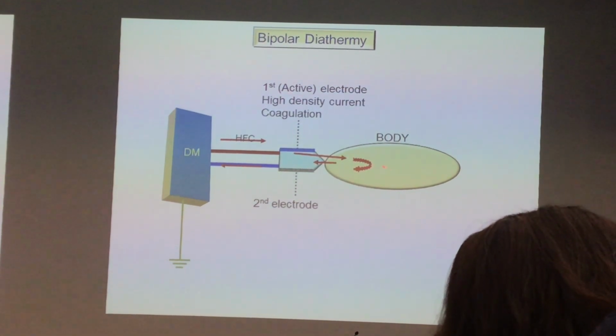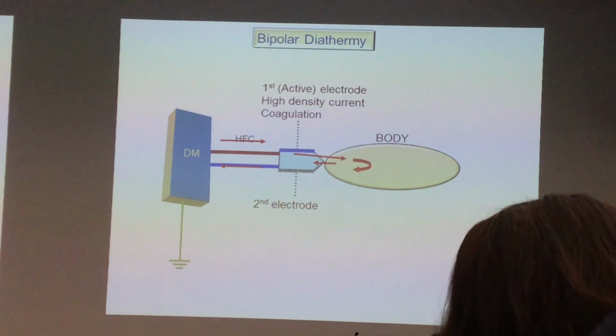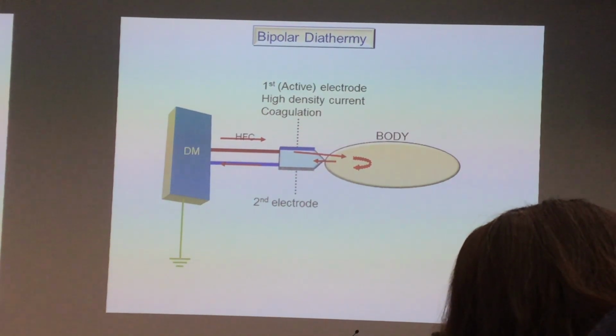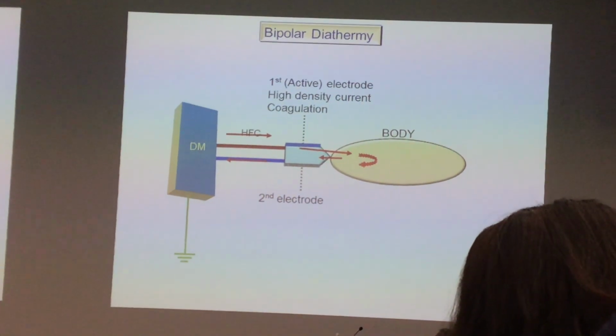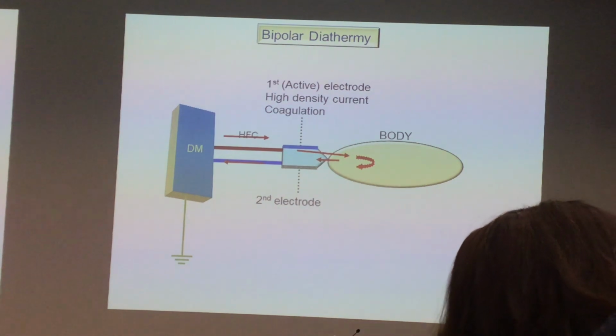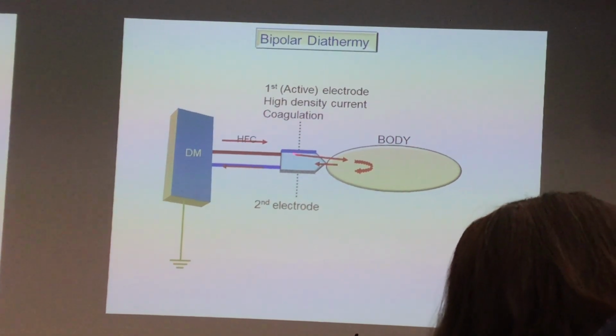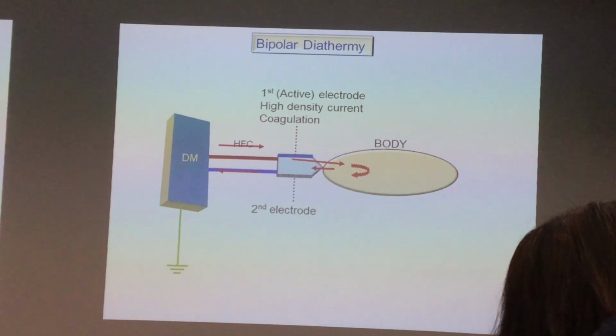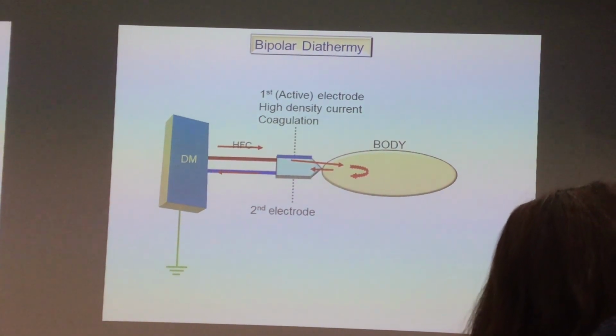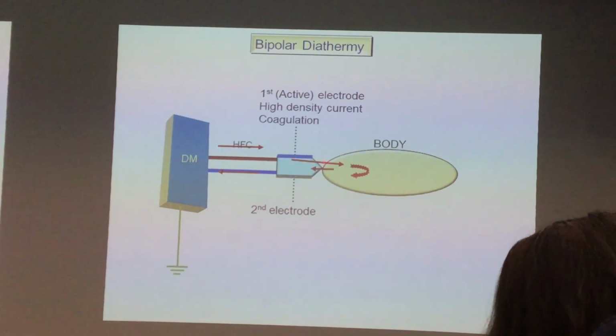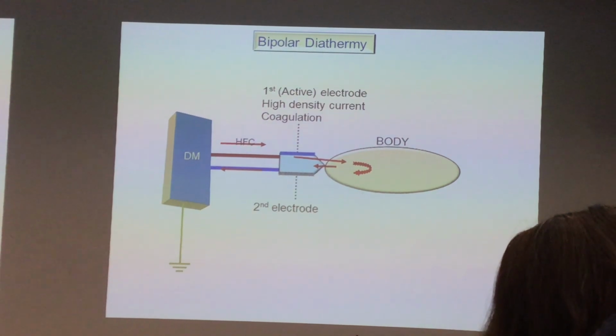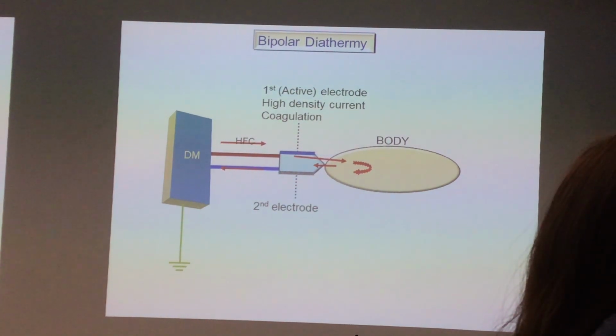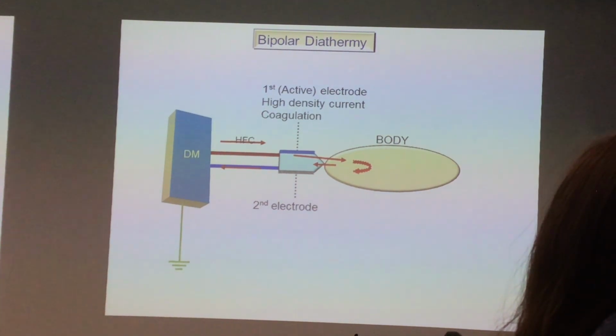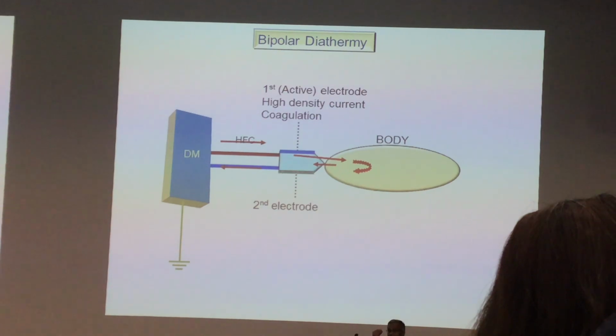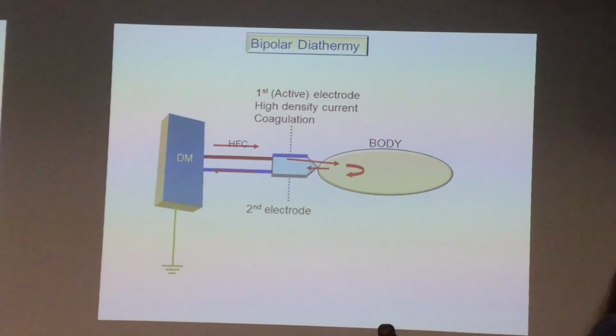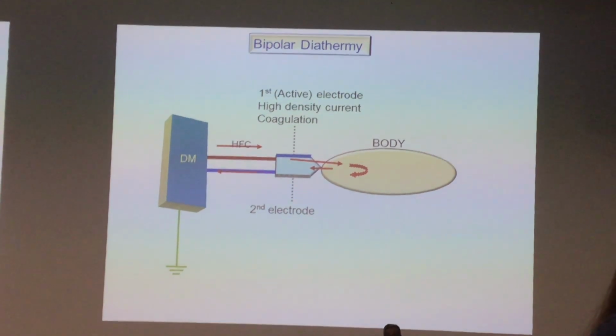In terms of frequency, I think this one needs higher frequency. So I just refresh: for cutting, you need lower frequency, 1 or 2 million hertz. For coagulation, you need higher frequency, up to 3 million. And the current does not pass through the body fluid to the diathermy plate and back to the neutral wire or cable. Therefore, this bipolar is only meant for coagulation. So it's not strong enough to cut the tissue, skin or bone. So for surgery like neurosurgery or eye surgery, anything where you don't have to cut, you can use bipolar. Understand? So it's not as good as unipolar.